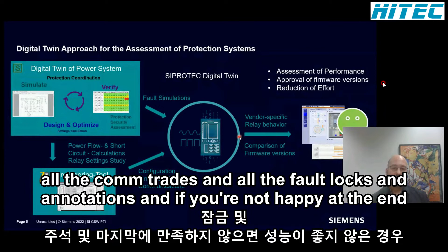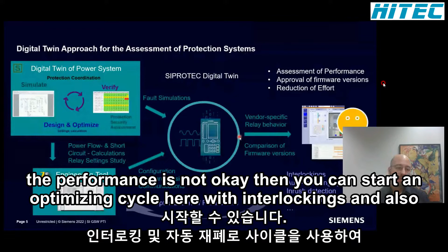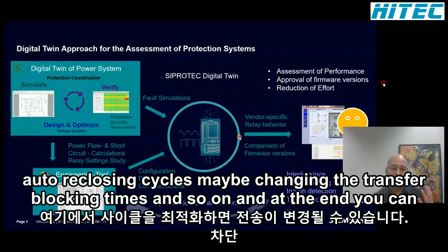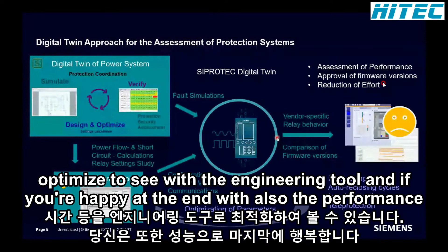And if you're not happy at the end, if the performance is not okay, you can start an optimizing cycle with interlockings and auto-reclosing cycles, maybe changing the transfer blocking times and so on. You optimize this with the engineering tool, and if you're happy with the performance, you can go back to your power system or relay database.